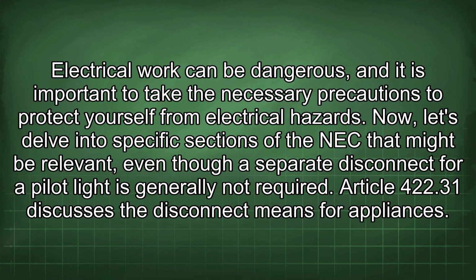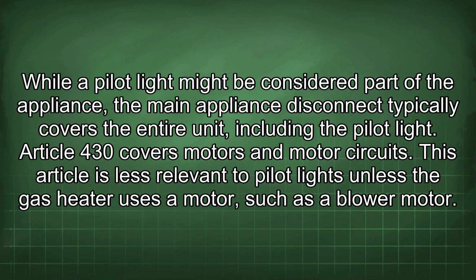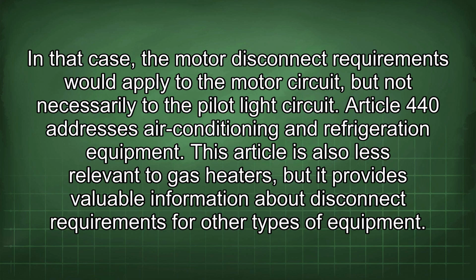Now let's delve into specific sections of the NEC that might be relevant, even though a separate disconnect for a pilot light is generally not required. Article 422.31 discusses the disconnect means for appliances. While a pilot light might be considered part of the appliance, the main appliance disconnect typically covers the entire unit, including the pilot light. Article 430 covers motors and motor circuits. This article is less relevant to pilot lights unless the gas heater uses a motor, such as a blower motor. In that case, the motor disconnect requirements would apply to the motor circuit, but not necessarily to the pilot light circuit.